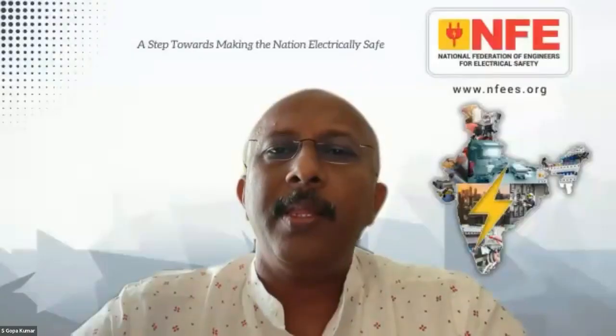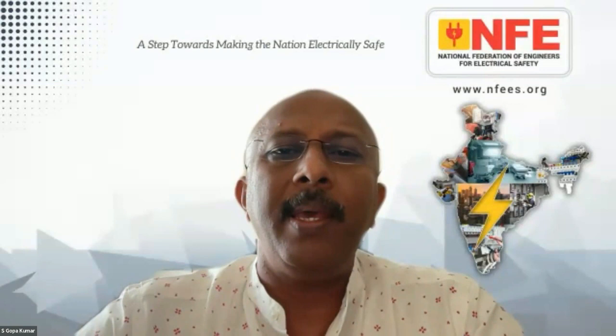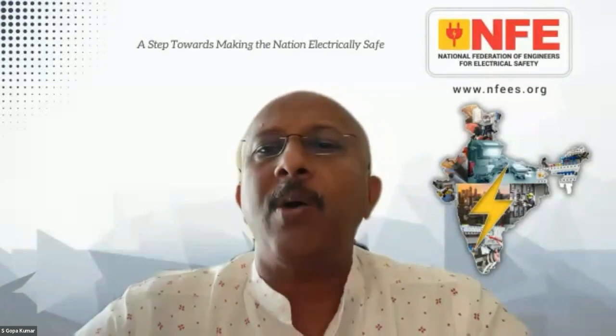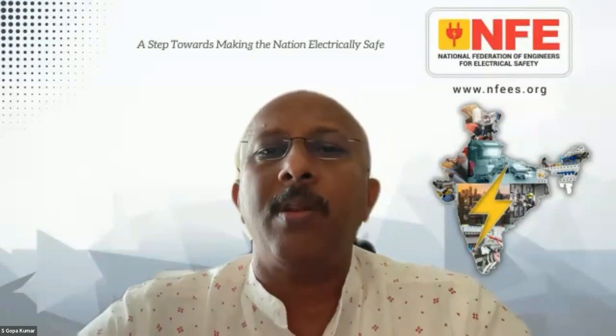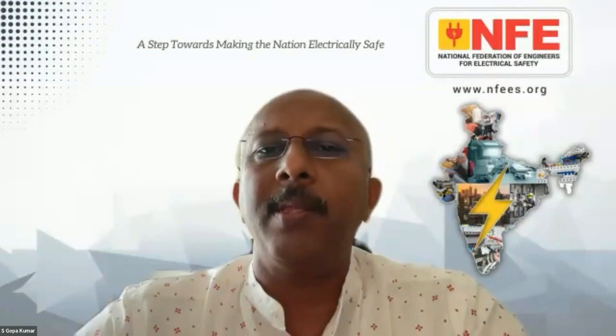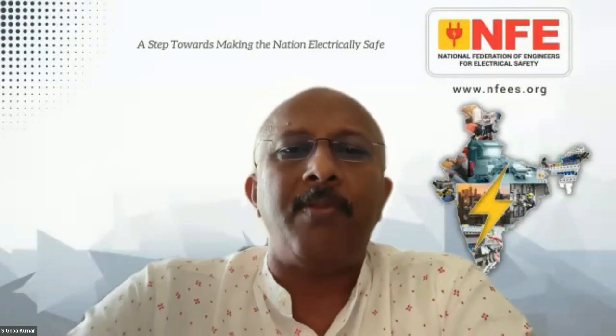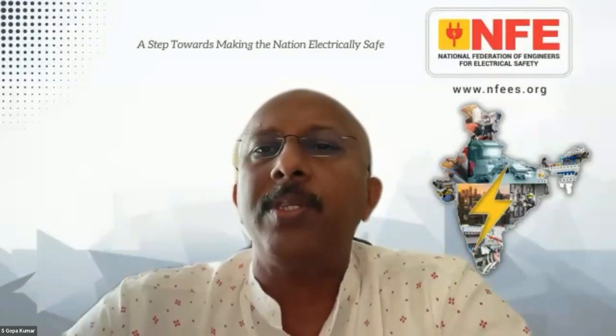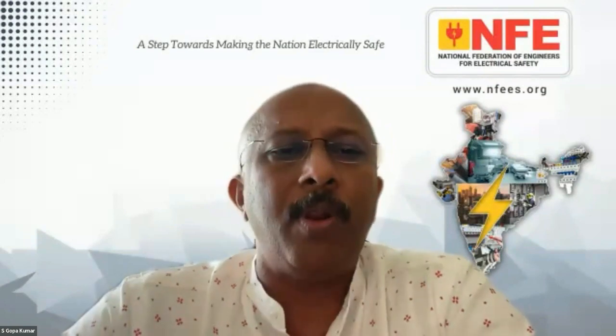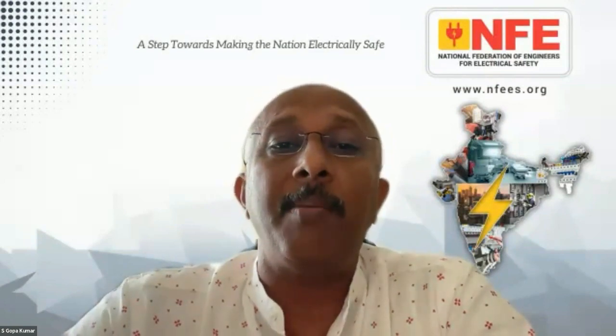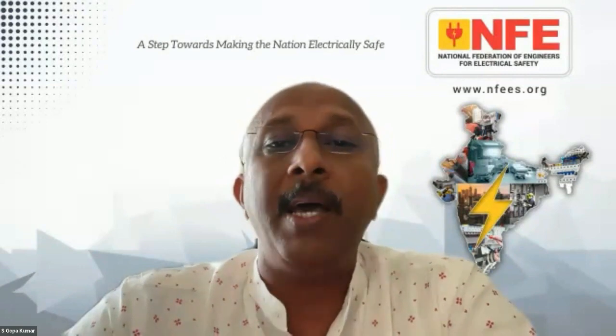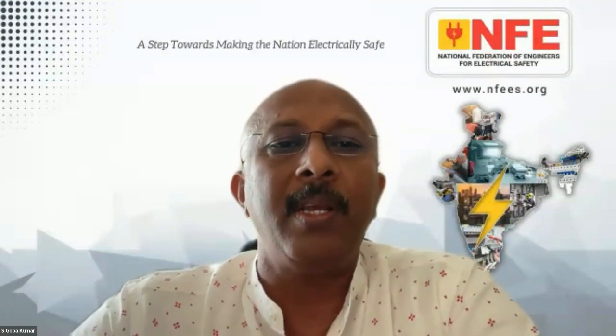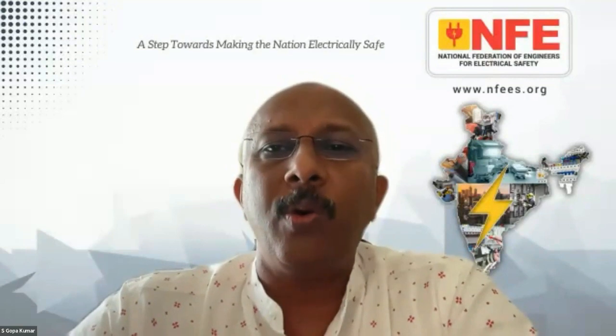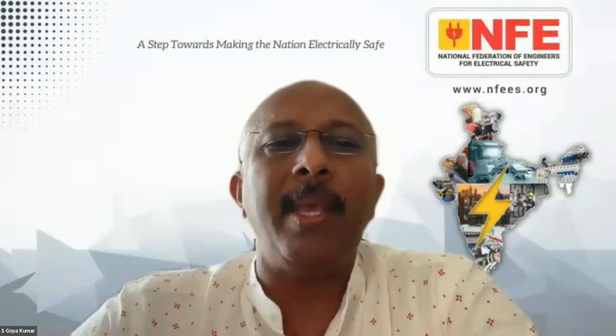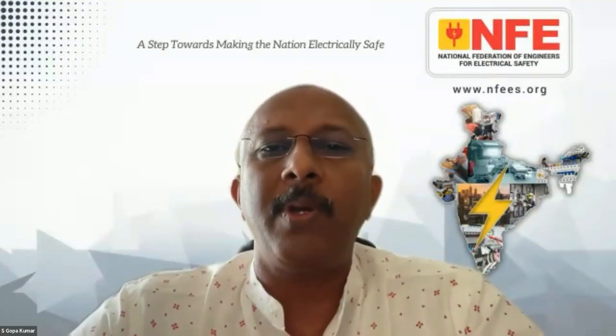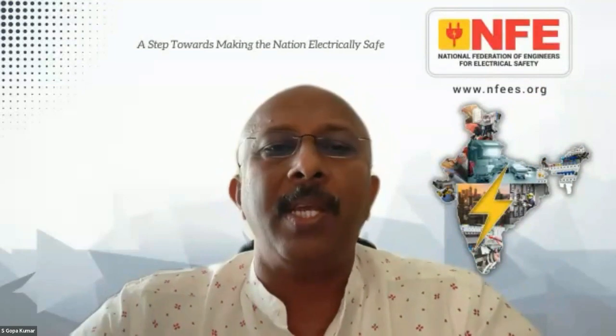I will reply. Actually, here the VFD manufacturers, for example ABB, have very good documents which very clearly explain how to handle this particular situation, shaft current or the leakage currents through the bearings, and how to make the bondings. All these are very well explained in the manufacturer's catalog. Refer to that. Also in the drive standards it is explained. But I have one more recommendation. Please refer to the international manual of these manufacturers, because in India the manufacturers are changing a lot of technical information and the correct information is not circulated. So go to their international website, download the manual of, for example, ABB ACS 500. Go to the Swiss or some UK website and download the manual. You will see pictures and the explanations.